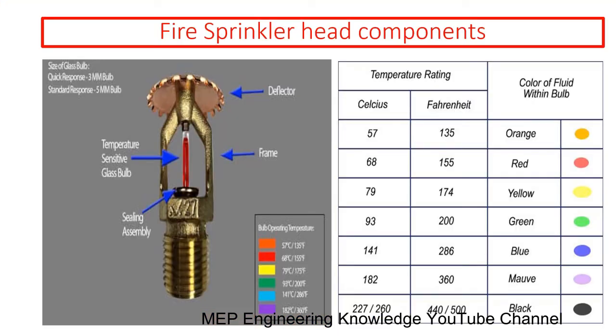Here we can see the sprinkler arrangements. In a sprinkler, we can see the sealing assembly, which is at the bottom. Next, there will be a temperature sensitive glass bulb. This will be of two types: one is 5 mm and another one is 3 mm. Quick response will have 3 mm and standard response will have a 5 mm glass bulb. Over that you can see a frame. Over that you can see the deflector, which is at the top of the sprinkler. And moreover, you can have different ranges of sprinklers, depending upon the temperature at which we need it to operate.